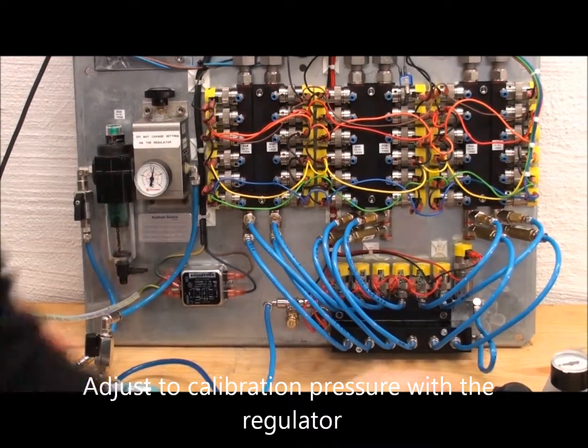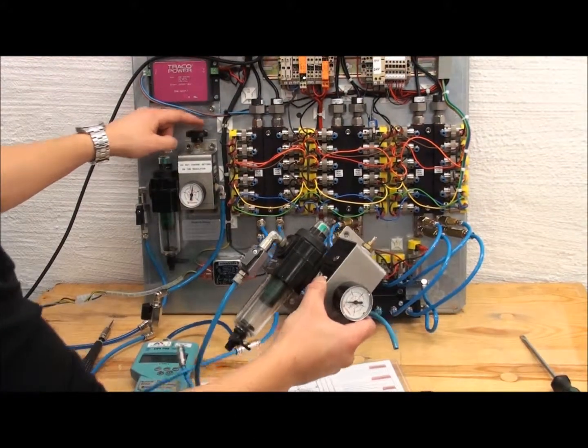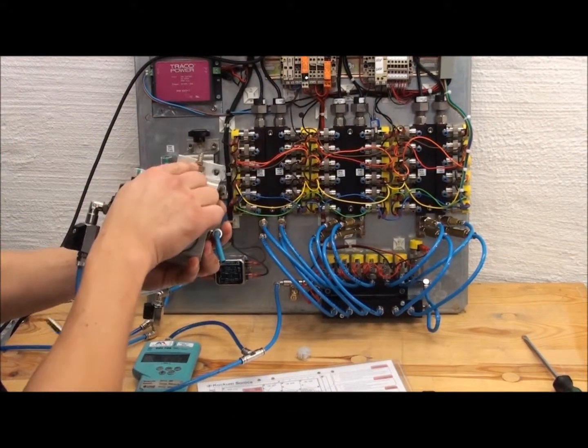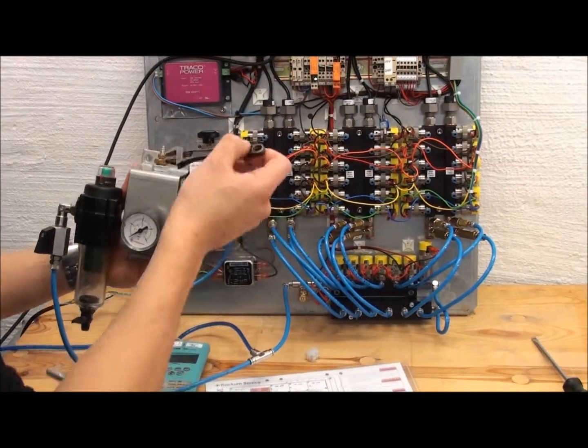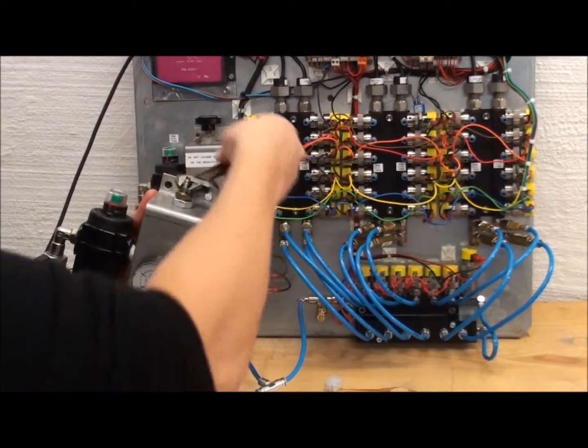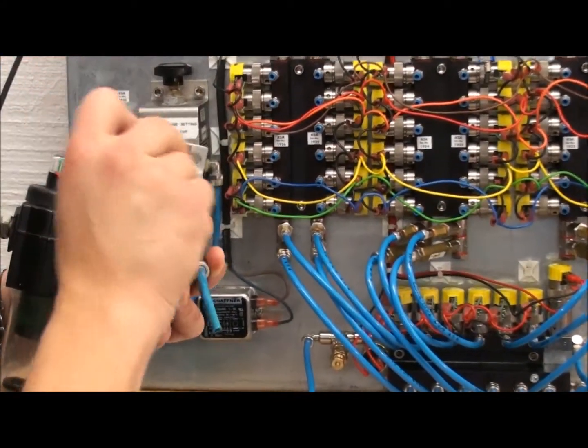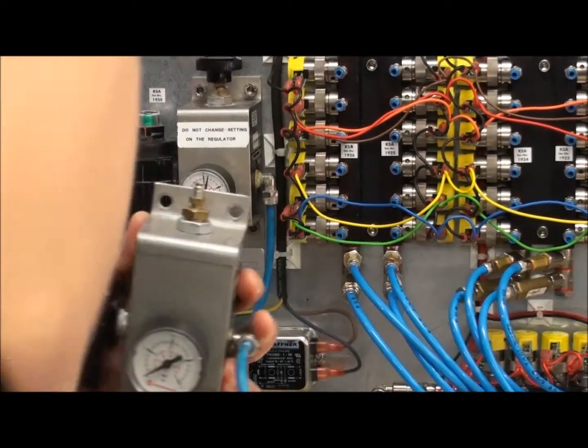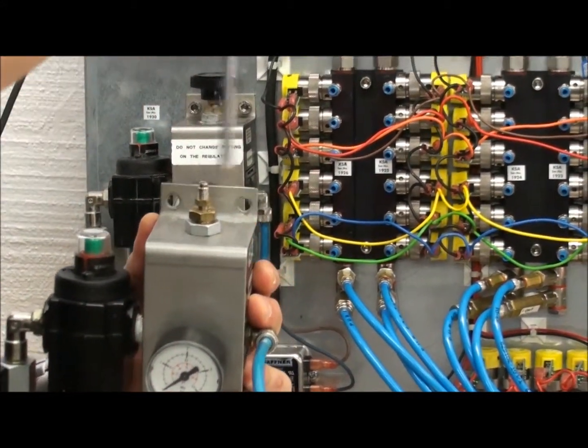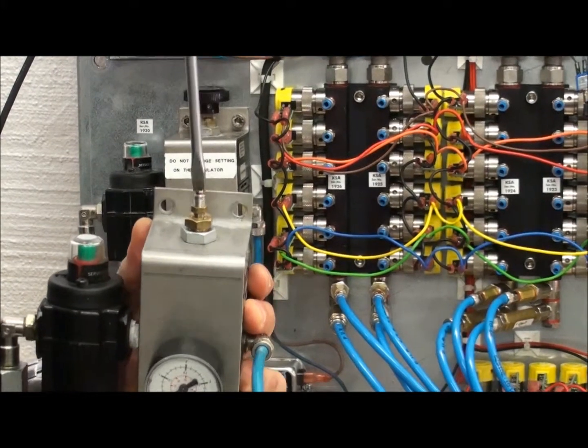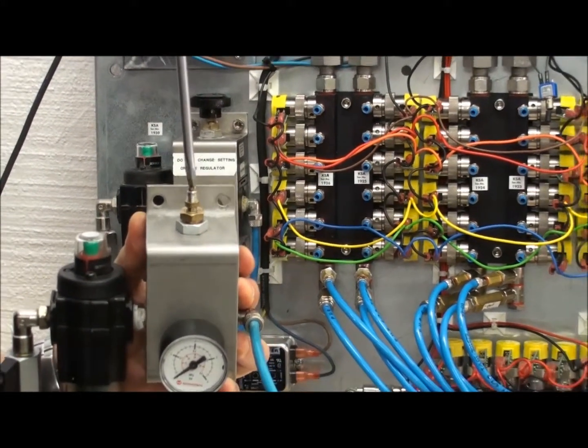Sometimes you don't have the cap on the regulator, but you have it like this. And the way to adjust it is that you should loosen this nut here, and then with a flat screwdriver you can adjust the pressure up and down. So if you don't have a cap, then you know what to do.